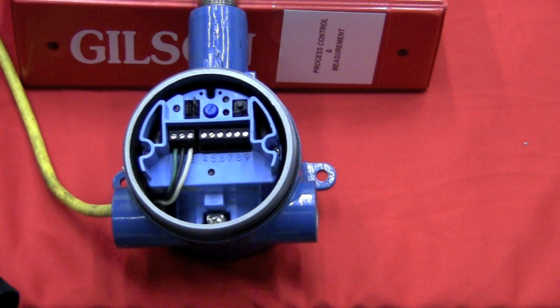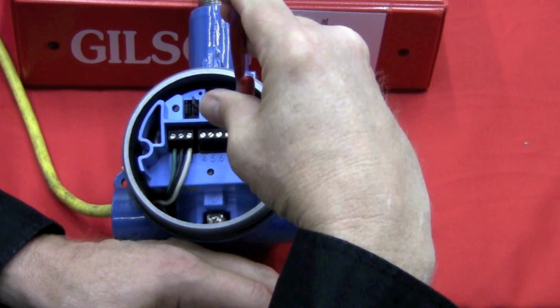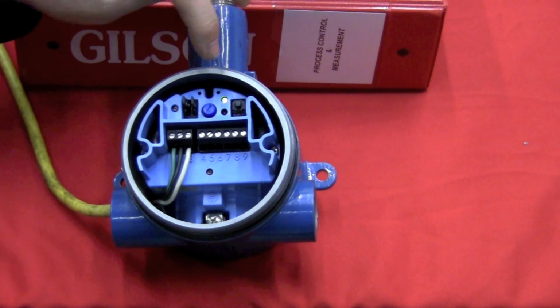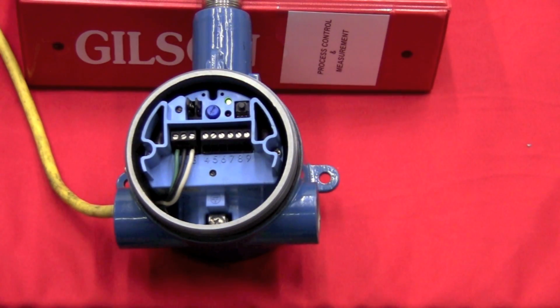You'll see that you're in mode 6. Once you're in the mode that you want to be in, you take your jumper off of these pins here, and put it back over in the position it was on the time delay. You'll see that your power light comes back on and you're not in alarm. Now that I've shown you how easy it is to select the mode, I'm going to show you how simple it is to calibrate the unit.